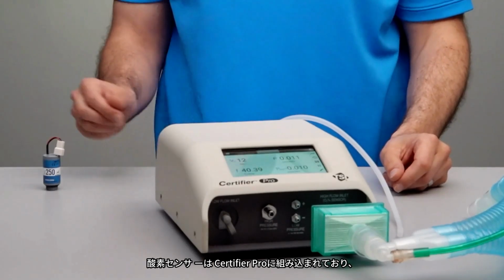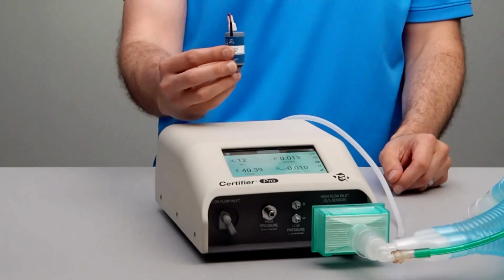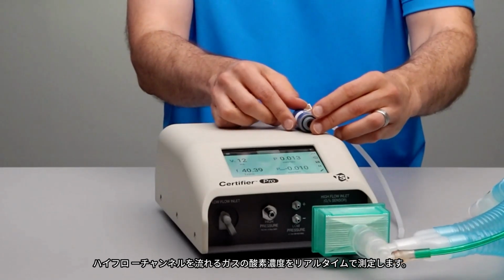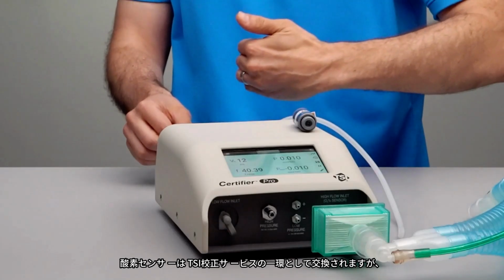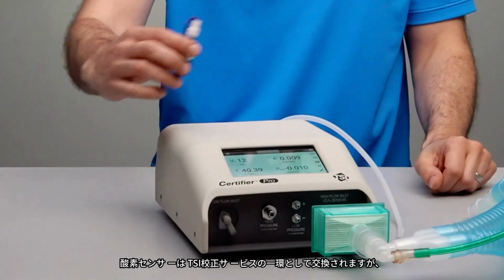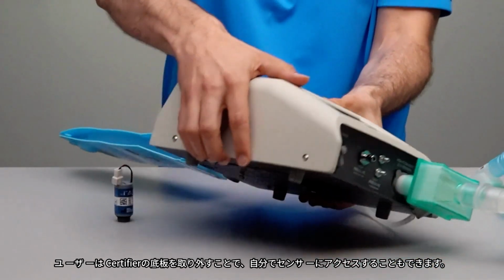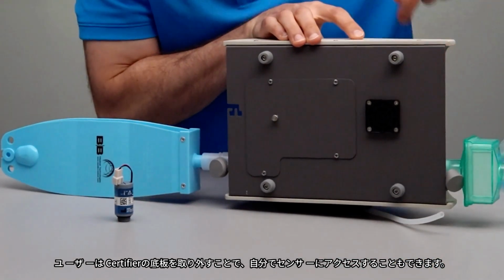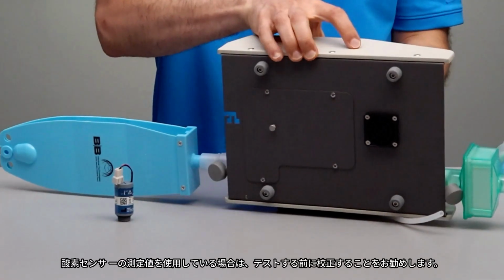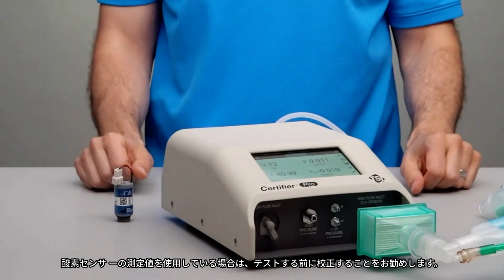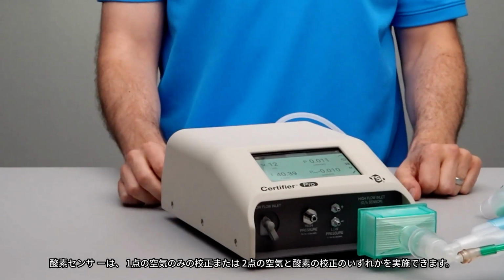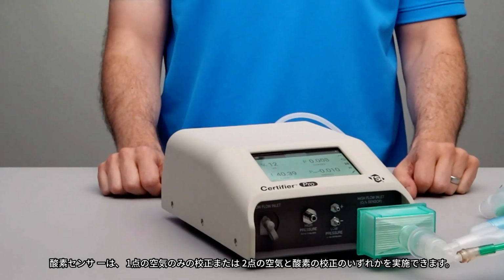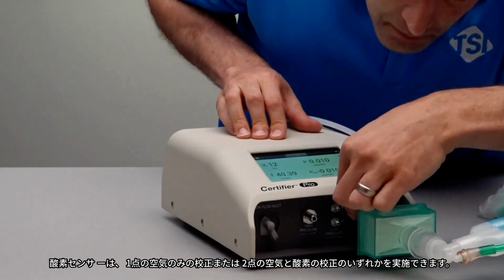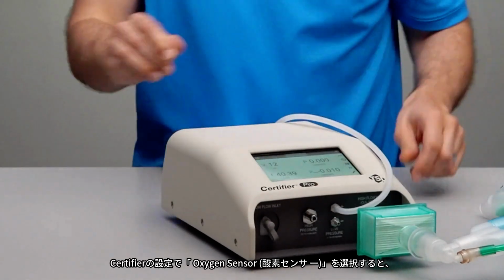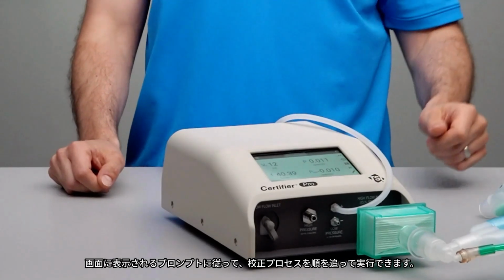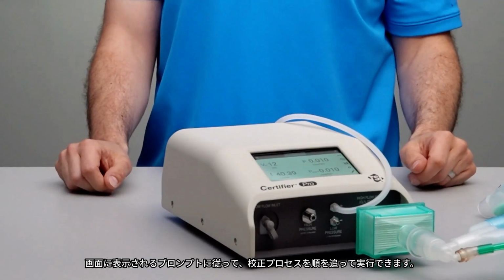An oxygen sensor is integrated into the Certifier Pro, and it measures the real-time oxygen concentration of gas flowing through the high flow channel. The oxygen sensor is replaced as part of TSI calibration service, or users can access the sensors themselves by removing the bottom plate of the certifier. If you're using measurements from the oxygen sensor, it's recommended that you calibrate it before testing. The oxygen sensor can be calibrated with either a 1-point air-only calibration or a 2-point air and oxygen calibration. Select oxygen sensor in the settings of the Certifier, and then on-screen prompts will take you step by step through the calibration process.